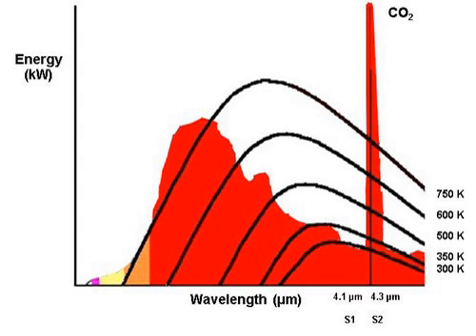The 4.3 micrometers CO2 peak in the picture is exaggerated, and is in reality less than 2% of the total energy of the fire. A multi-frequency detector with sensors for UV, visible light, near IR and/or wideband IR thus has much more sensor data to calculate with and is therefore able to detect more types of fires and to detect these types of fires better: hydrogen, methanol, ether or sulfur.